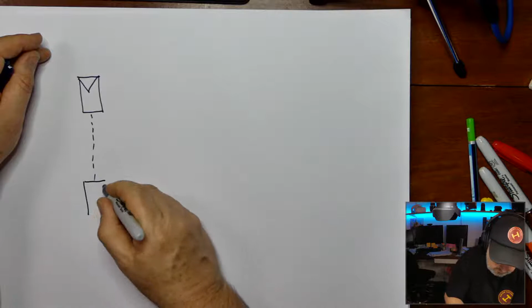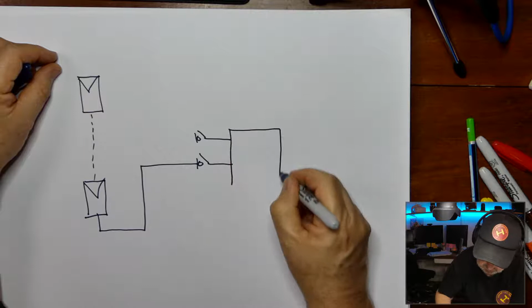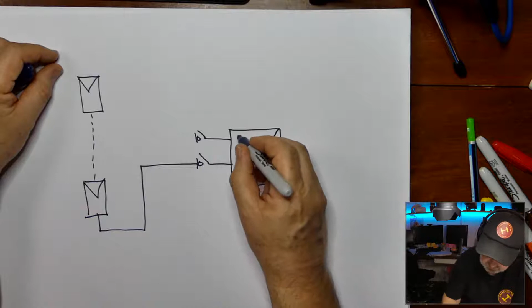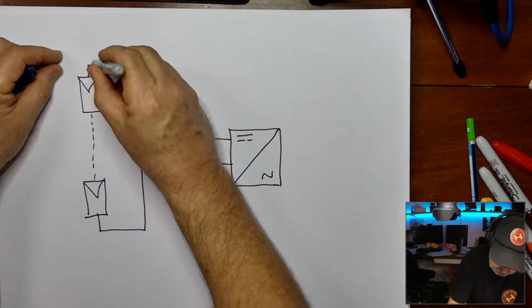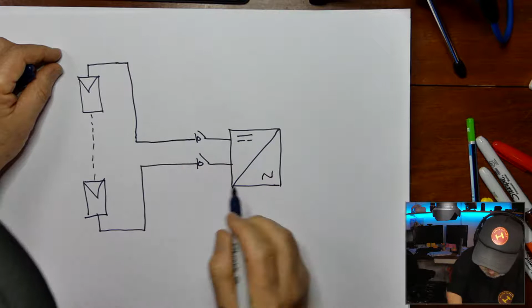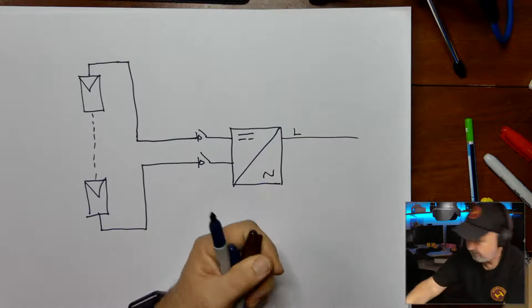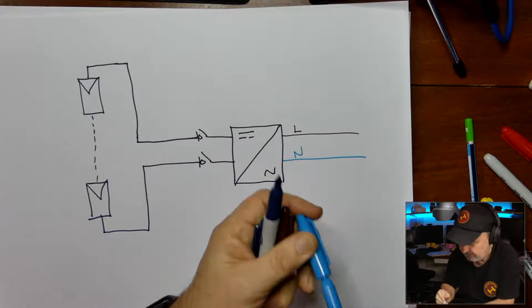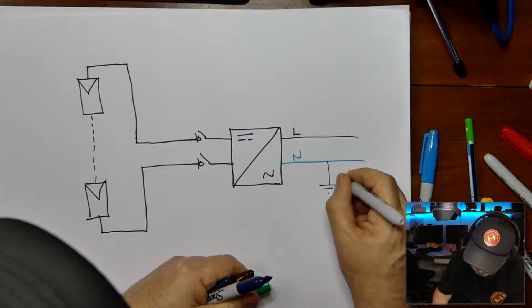Okay. So the question I think that Joe's asking is about the voltage rating of DC isolation devices, in a PV array particularly. I'm just going to draw a simple PV array here with a single point of isolation. Here's our isolation device, and it's load breaking, and it's connected to a transformerless inverter. If you're wondering what a transformerless inverter is, almost all inverters now are not galvanically separated from the AC side. They rely on their internal electronics to protect against possible earth fault problems, and so they have inbuilt earth fault alarms. Here's our live, there's our neutral going out this side, and good old MEN to earth down here. That's our MEN point.